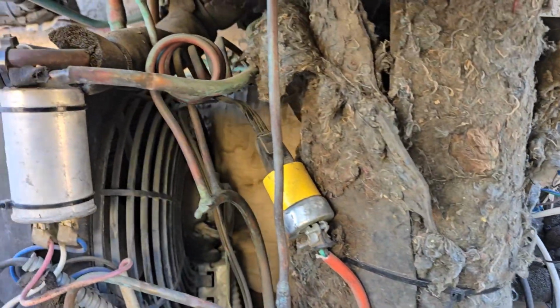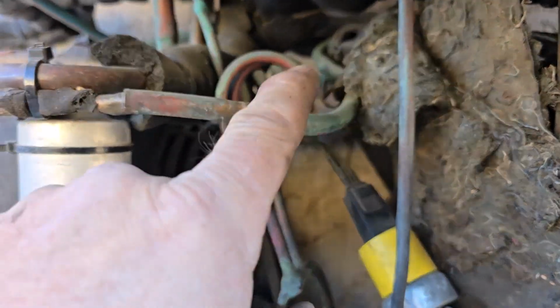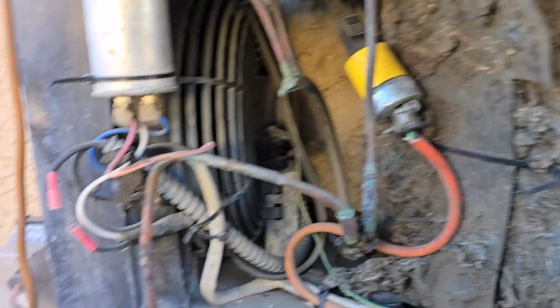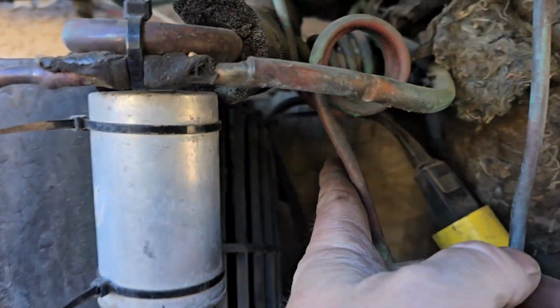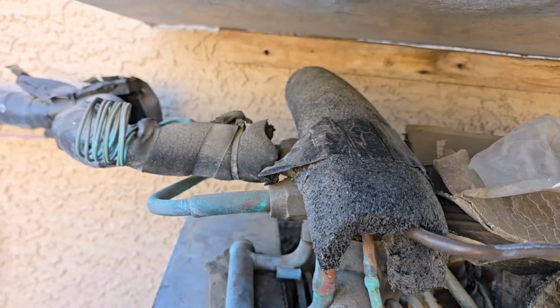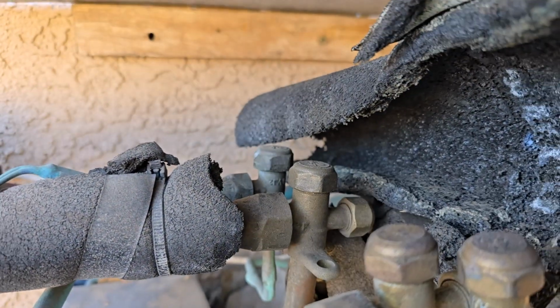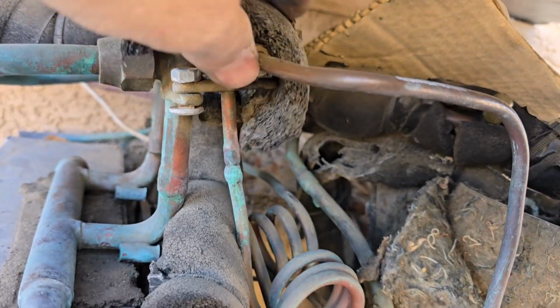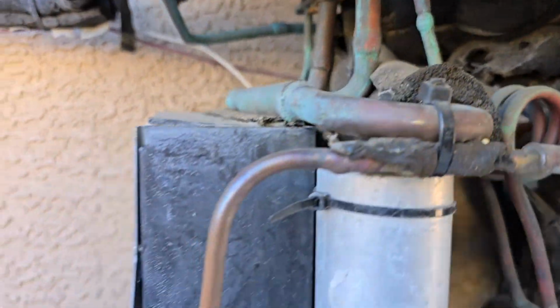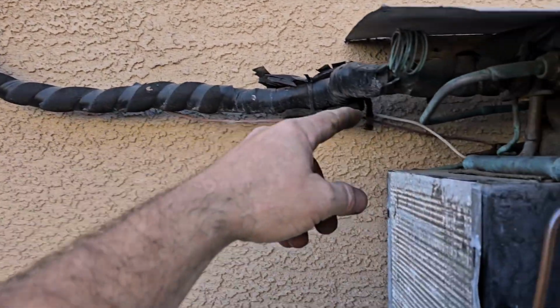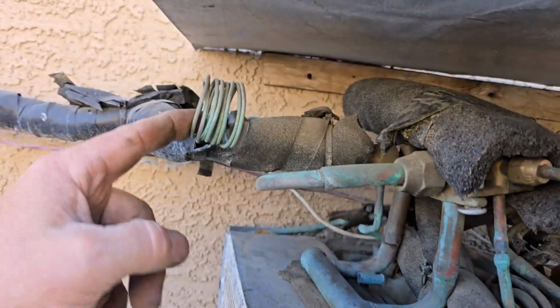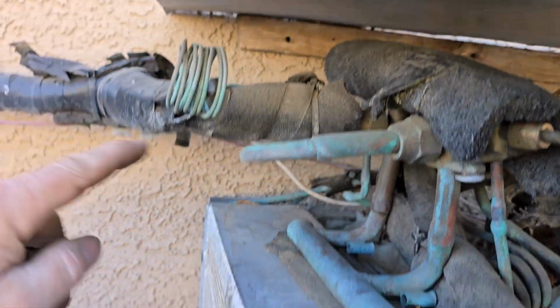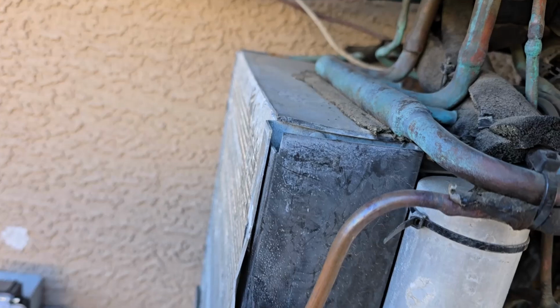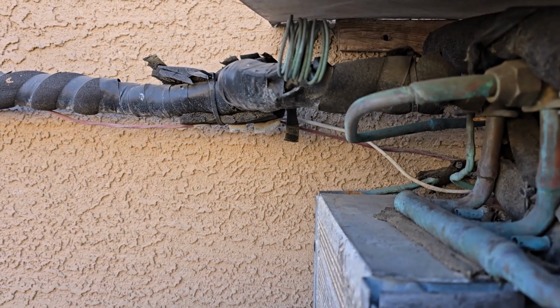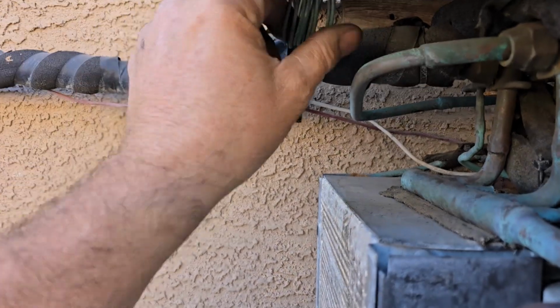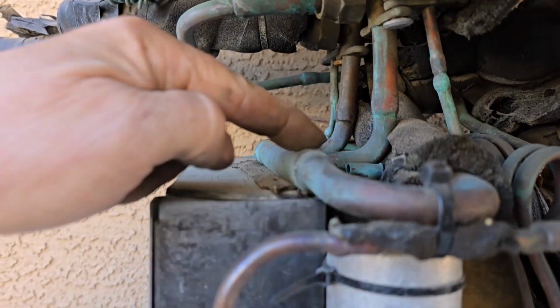So it comes out after that heat exchanger, comes out from here, and then it goes down. How do I got it? It goes up and it feeds these, splits the 2 circuits. And what I have here is leftover from ductless stuff. I have 2 circuits, and I just use them for isolation pump down valves. So right now I'm using that high wall in there. And I just have it going through the liquid line, through a capillary tube right here into that liquid line, and this capillary tube is perfect. And I've been getting like a 39-40 degree coil now that it's been down into the 60s in that room in there. And then the suction comes back here.